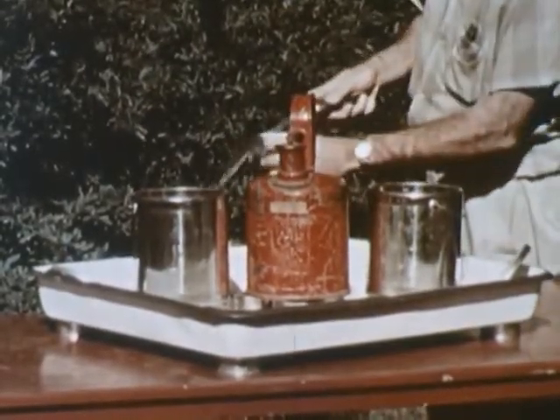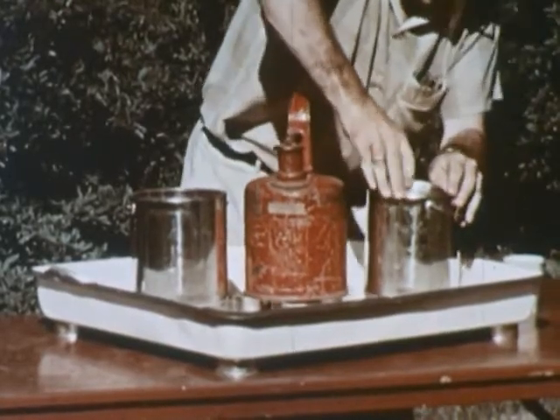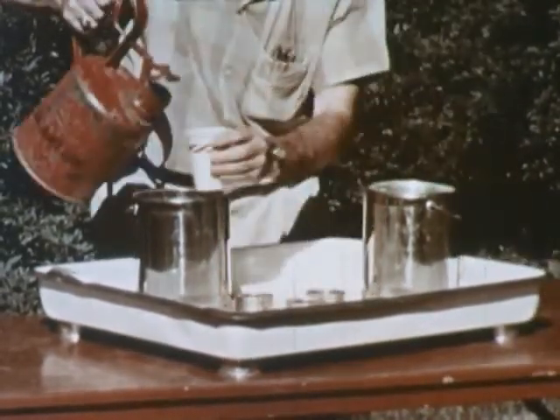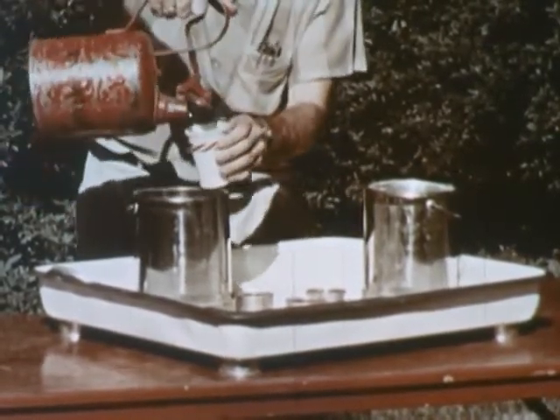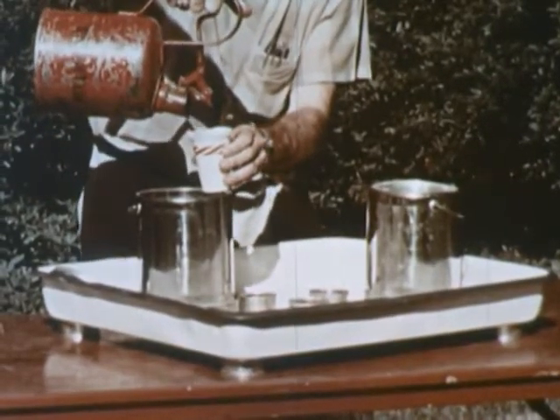The importance of emergency venting can be demonstrated on a small scale. A small amount of water is placed in a gallon can, and an equal amount of gasoline is placed in another can. The same amount of gasoline is placed in a third can, which has a small hole punctured in the top to serve as an emergency vent. The unvented cans containing the water and gasoline fail approximately at the same time from overpressure. Pressures in the third can are safely relieved, as are the pressures in storage tanks equipped with emergency venting.